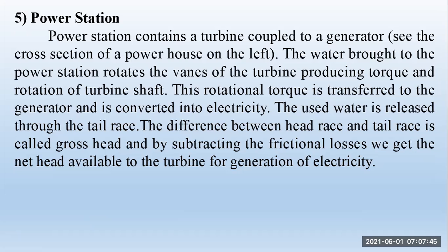The used water is released through the tail race. The difference between the head race and the tail race is called gross head. By subtracting the frictional losses, we get the net head available to the turbine for generation of electricity.